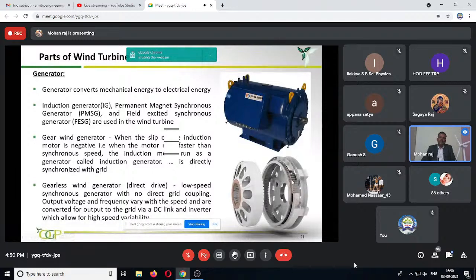The rotor is normally a permanent magnet, or maybe a field winding excitation. Okay, so as I said, the gearless wind generator is a low speed synchronous generator with no direct grid coupling. Because, as I said, the induction generator will directly couple to the grid without any conversion, because it will generate power which matches the grid. For example, 440 volt and 50 hertz, it will automatically pump to the grid.